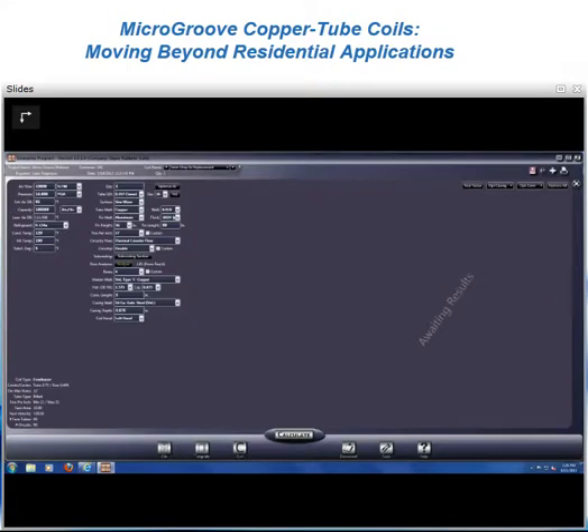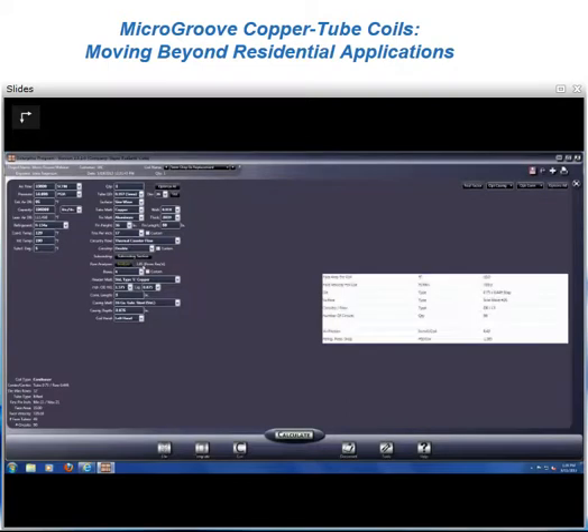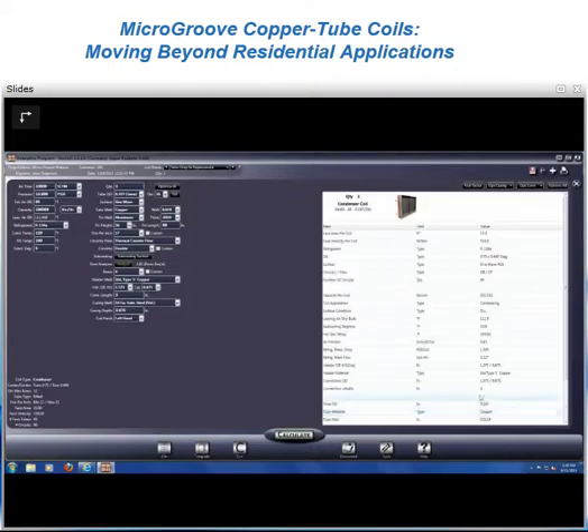As John mentioned, we're going to now go with an 010 wall thickness. Because of the smaller diameter, the thinner wall thickness is what we need for this pressure. Aluminum fins at 0039 and the same physical dimensions. Our fins per inch will go up slightly to 17, and we've input our circuiting information. So we'll analyze that, 3.85 rows. Let's rate that as a 4-row coil.